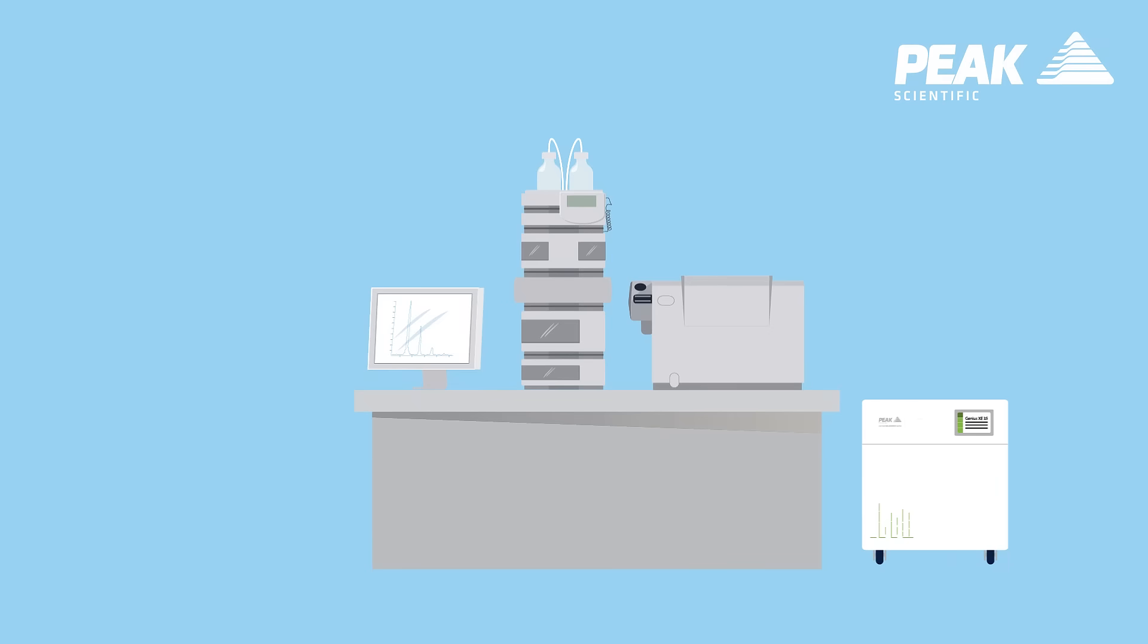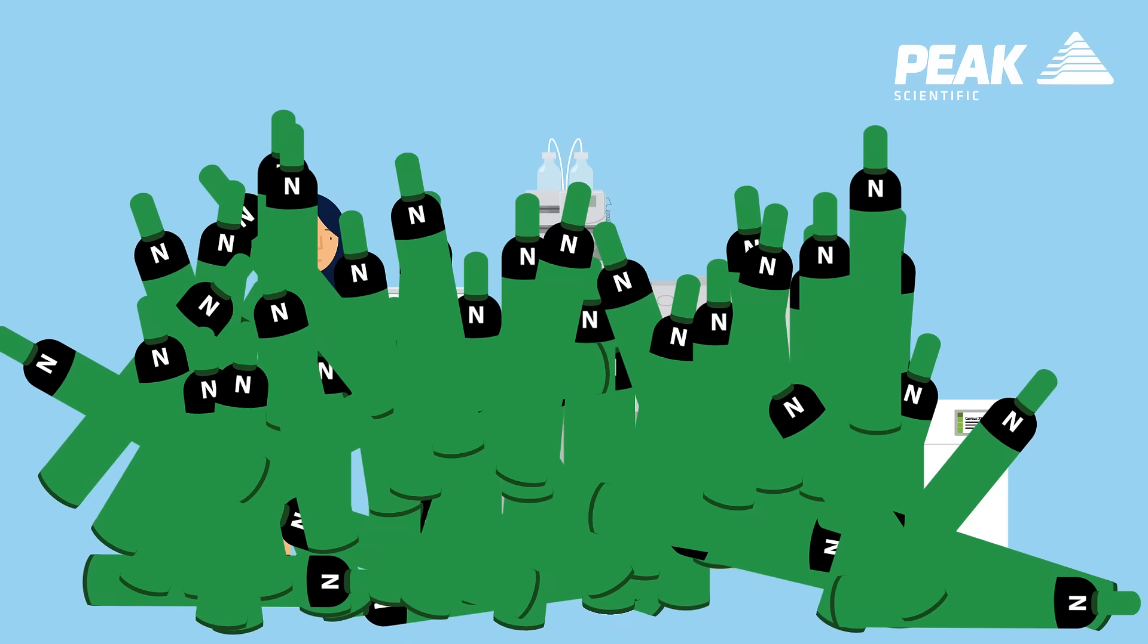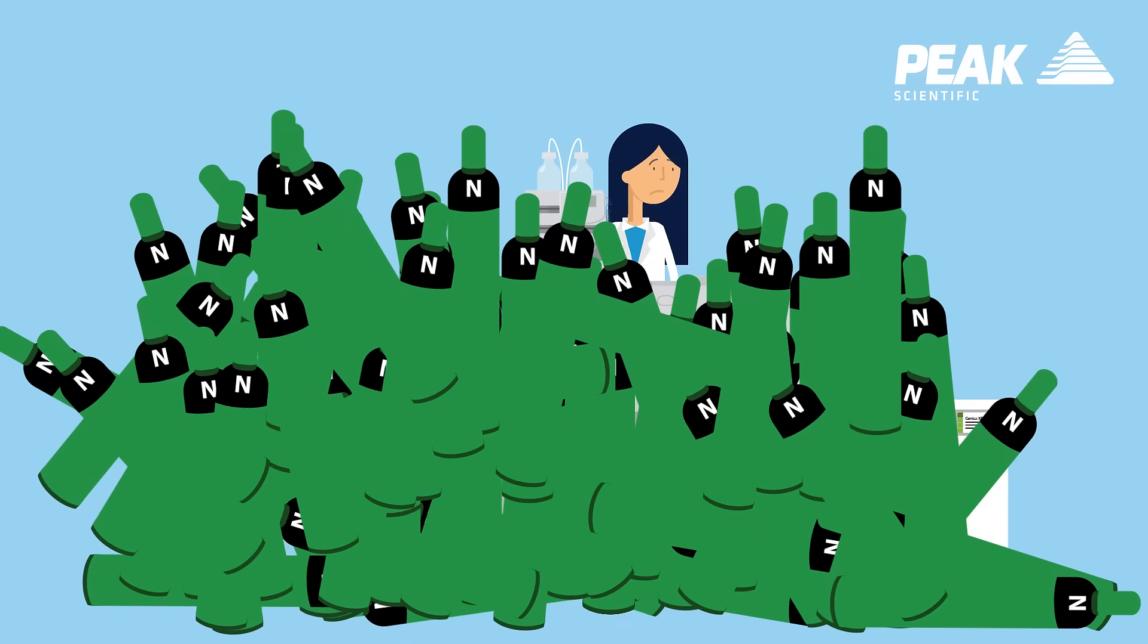Gas generators are both efficient and help reduce a lab's carbon footprint. For example, a nitrogen generator that produces 32 liters of nitrogen per minute will produce over 4 million liters of nitrogen before needing to be serviced. This is the equivalent to over 400 nitrogen cylinders that would require transportation from the cylinder depot to the lab.